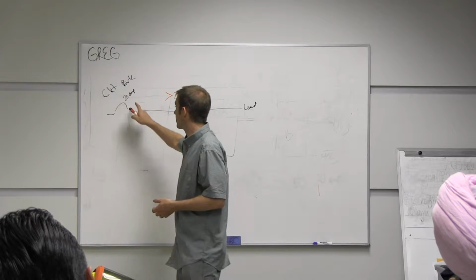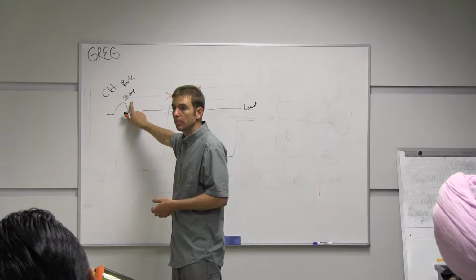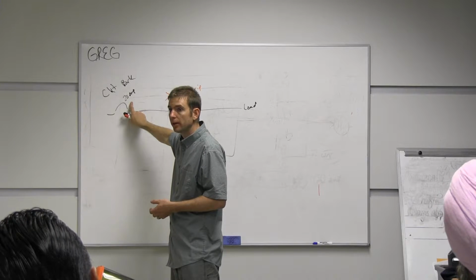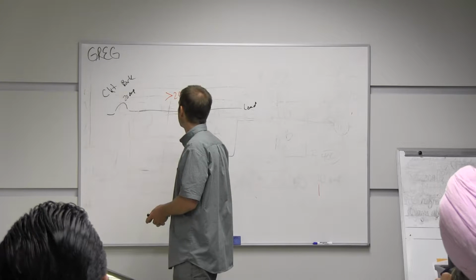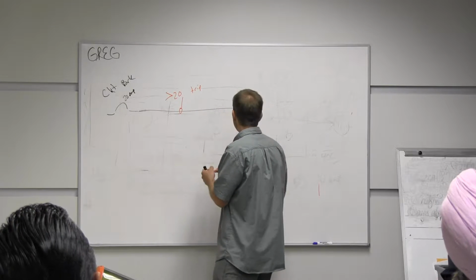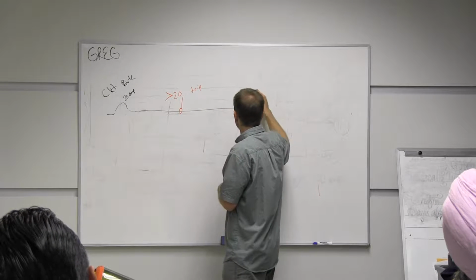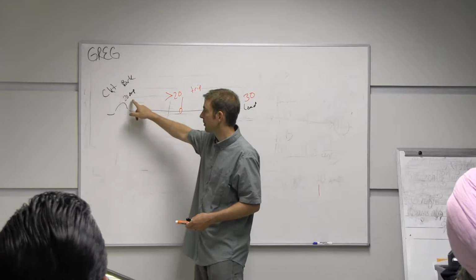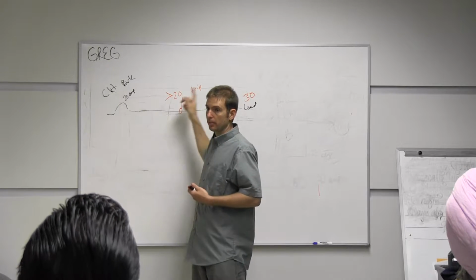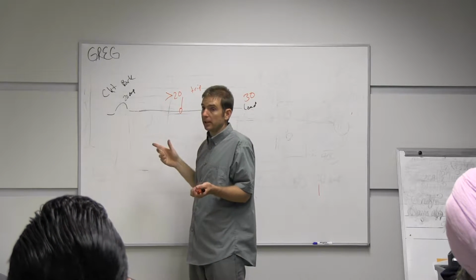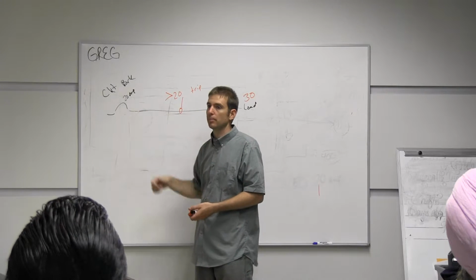If you put a 20 amp circuit breaker on a circuit that has 30 amp wire? Yeah. Oh, okay. So if I had a 30 amp load and I didn't have a 30 amp circuit breaker or something that would accommodate this load, and I said, well, I have a 20 amp, I'll just replace it with a 20, it's going to trip all the time. Oh.